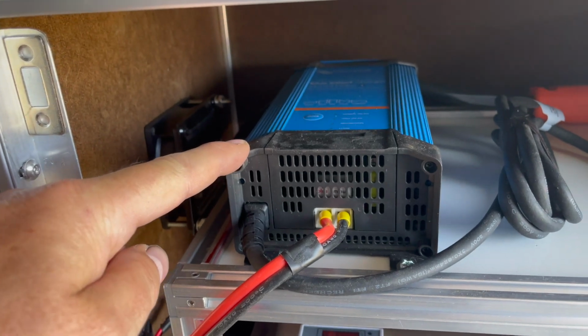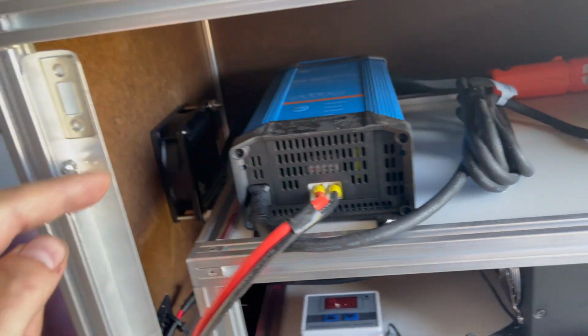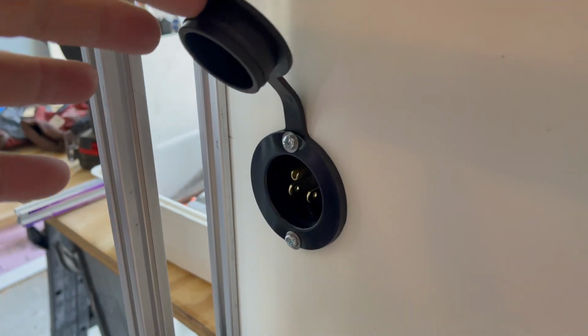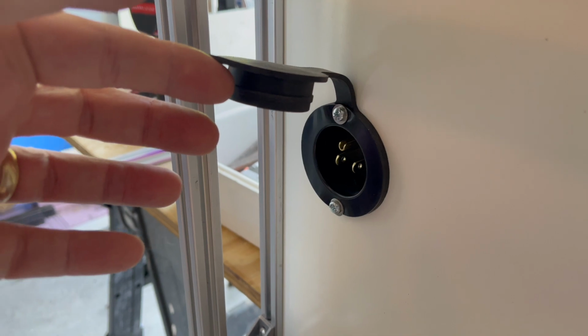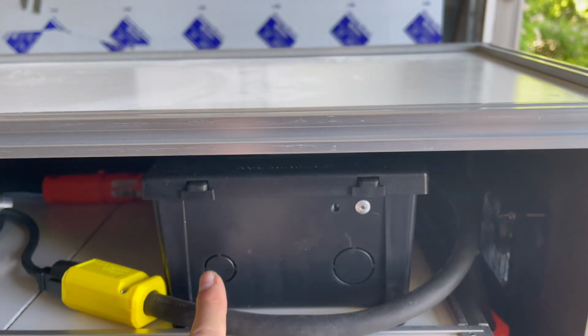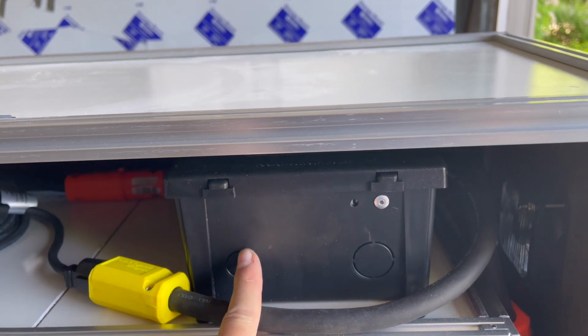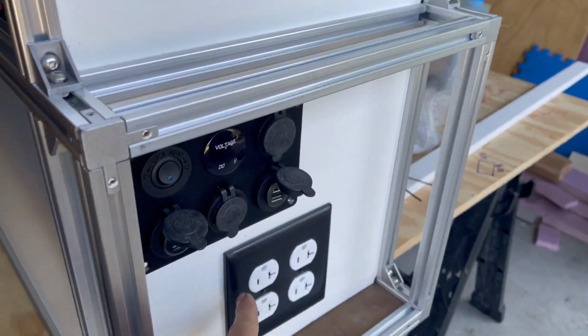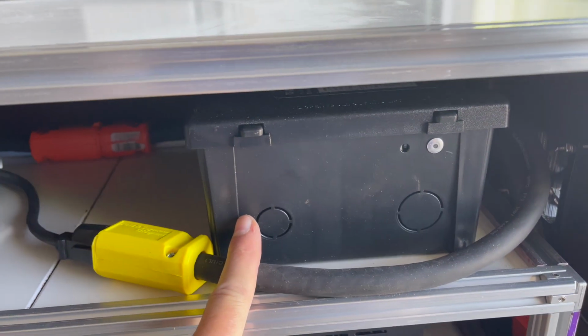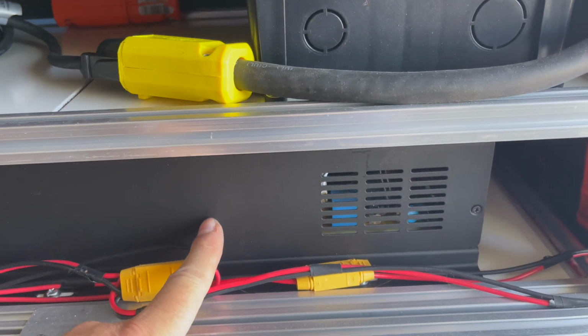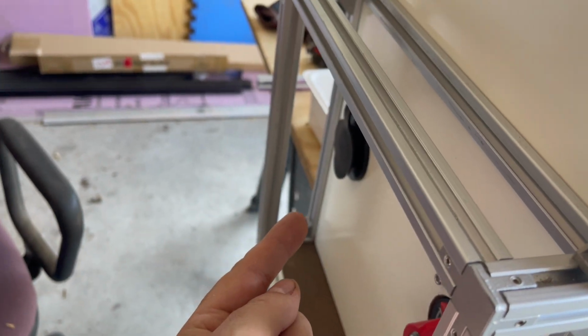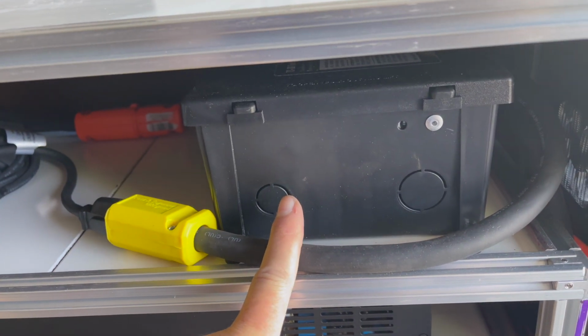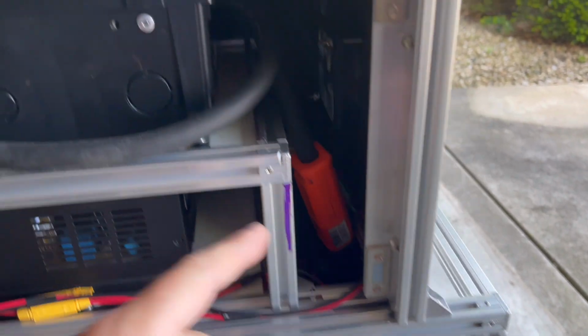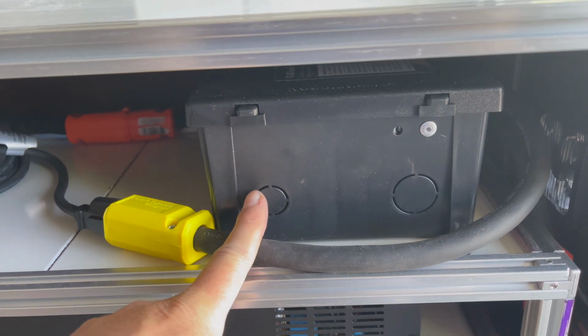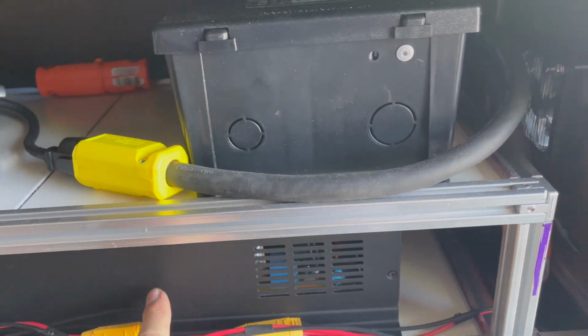This is a Victron smart battery charger. That plugs into the AC of your house and will charge the battery via the AC. Then there's an automatic transfer switch. This automatic transfer switch has one output, which powers these outlets right here, but it has two inputs. One input is from the actual inverter, and the other input is a pass-through from the house, that outlet right there. It senses if the house power is on, and it passes through to those outlets. If the house power gets interrupted, then the battery powers the inverter, and the inverter powers those outlets.